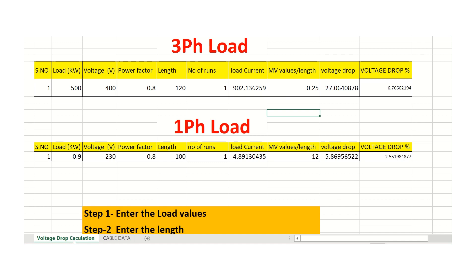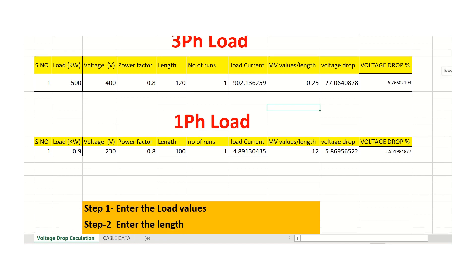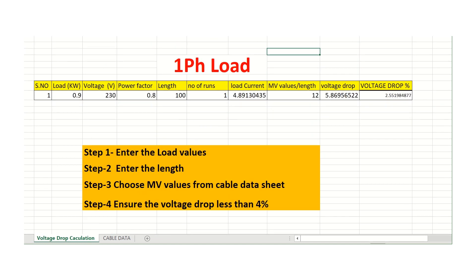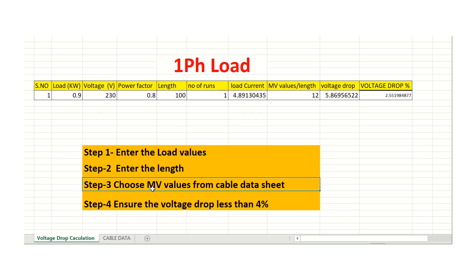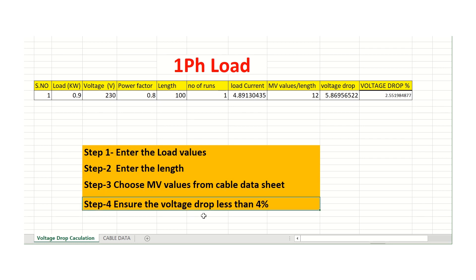Now let's go back to the voltage drop calculation. The formula is MV × I × L divided by 1000, and all those values will be fed into this Excel sheet. There are four steps: first, enter the load values; second, enter the length; third, choose the MV value from the cable data table; and fourth, ensure the voltage drop is less than 4%. Following these four steps, you can automatically calculate each and every cable size.